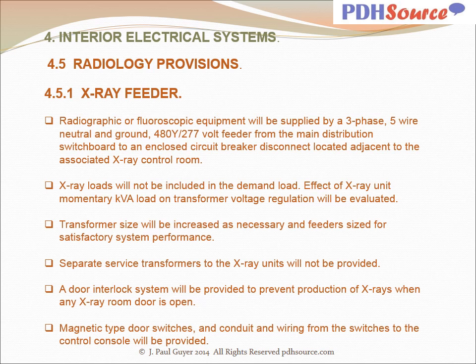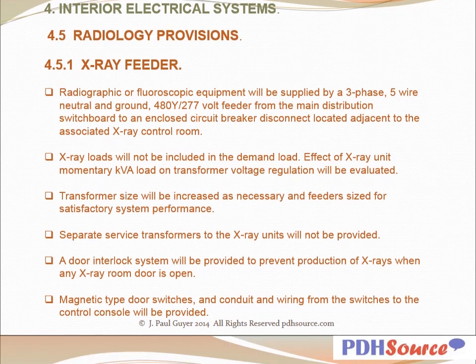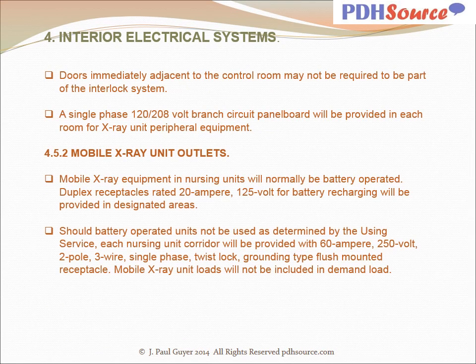A door interlock system will be provided to prevent production of X-rays when any X-ray room door is open. Magnetic type door switches and conduit and wiring from the switches to the control console will be provided. Doors immediately adjacent to the control room may not be required to be part of the interlock system. A single phase 120-208 volt branch circuit panel board will be provided in each room for X-ray unit peripheral equipment. Mobile X-ray equipment in nursing units will normally be battery operated. Duplex receptacles rated 20 amp 125 volt for battery recharging will be provided in designated areas.